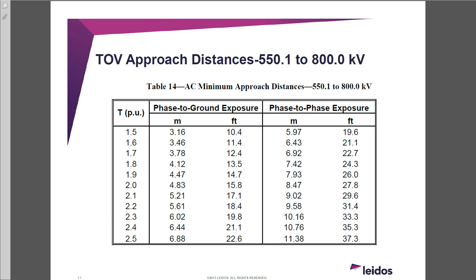Before we even get there, per unit values greater than 3.5 that we've actually witnessed, we've called other utilities and they're like, oh yeah, we've done EMTP studies and we're at 4 per unit. You have another special equation you can put inside the OSHA calculation, and it's pretty clear where it is in OSHA that you can calculate all these values.